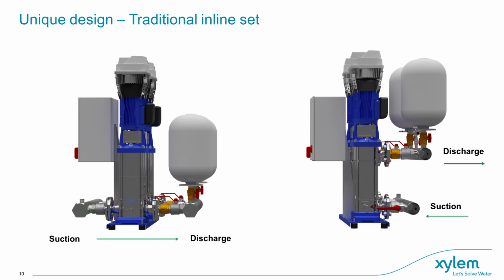Now in this slide we can compare the difference between the GHVR set on the right to a traditional booster set on the left. The majority of all booster sets on the market use the inline configuration. However, as previously mentioned, the GHVR booster set has a suction and discharge manifold on the same side, giving it a more compact design.